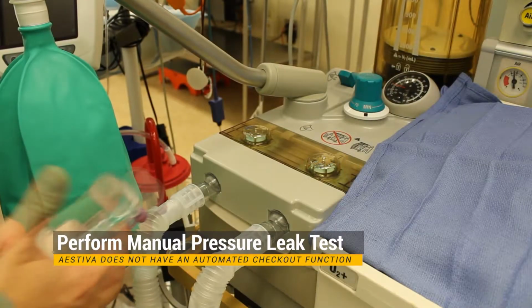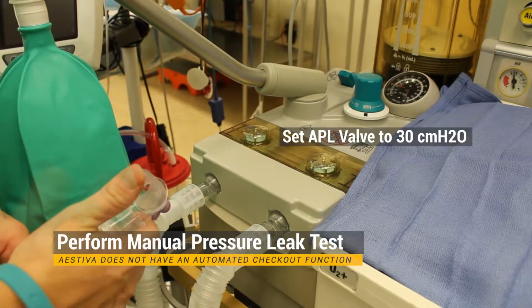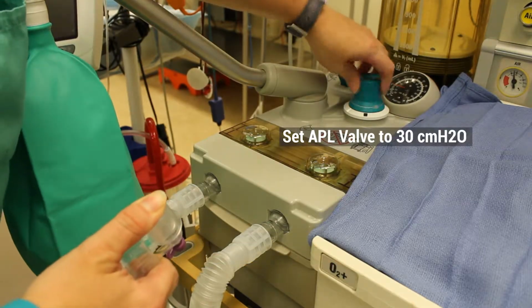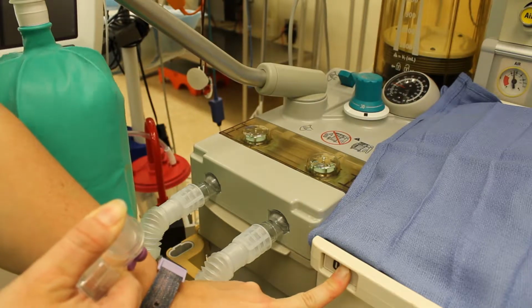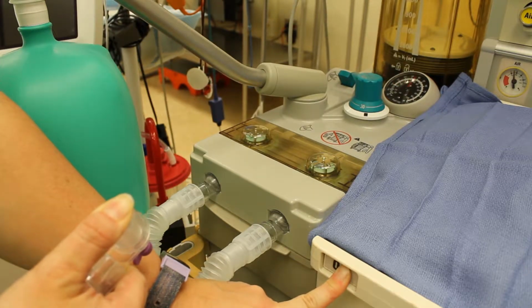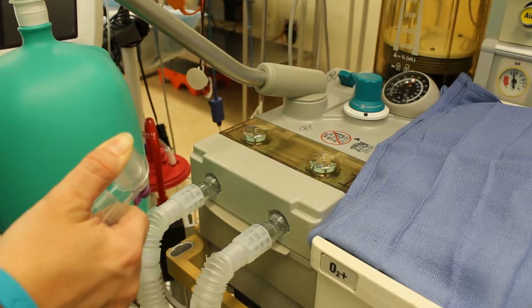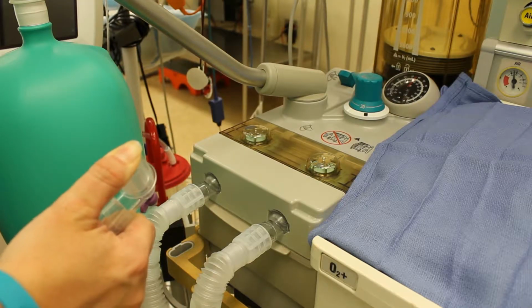Connect a new circuit to the anesthesia machine and perform a pressure test. In order to check it manually, ensure that all gas flows are off, occlude the Y-piece, set the APL valve to 30 centimeters of water, press and hold the O2 flush valve until the system pressure stabilizes. It should not exceed 45.